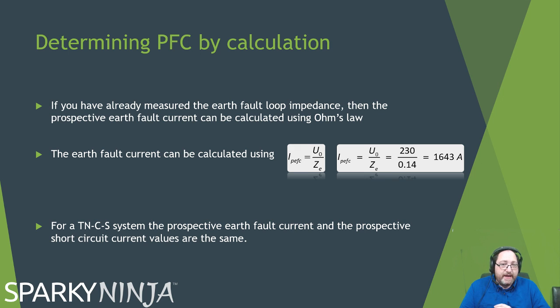And if you mistakenly go with calculating from ZE, then you may end up saying, oh, that's fine, it's 8.7 kA, the 10 kA devices are fine, but when the parallel circuits are introduced, it could go up above 10 kA. That's no good. Alright, so what you need to do is understand the difference between measurement and calculation. Calculation is crap.